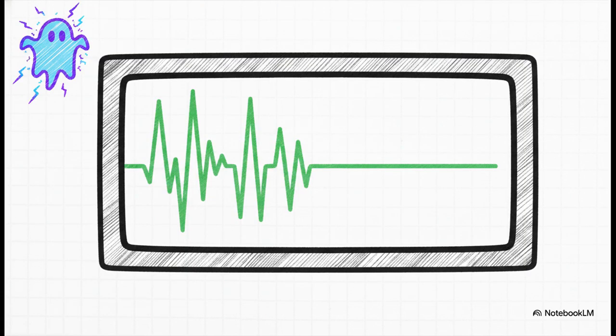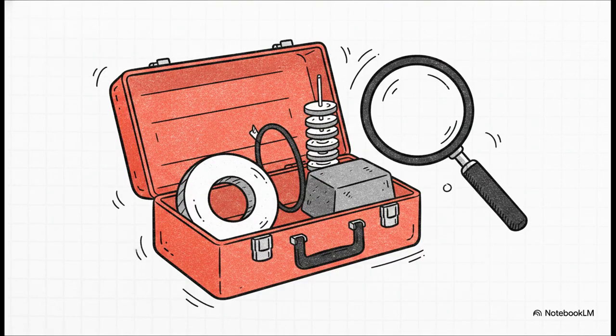If you guessed a traditional VT, you hit the nail on the head. That specific transient spike and settle pattern happening right after a switching operation is the absolute signature of ferroresonance. A resistive divider physically cannot produce this kind of erratic behavior because its linear coreless physics simply do not allow for magnetic resonance. So, if you see a phantom fault spike like that, you know exactly what hardware is sitting behind the panel. All right, let's bring this all together.